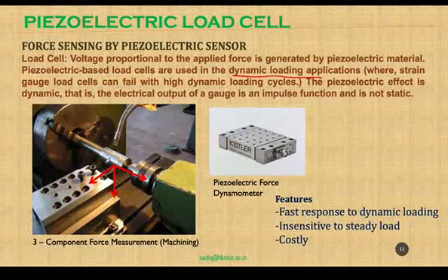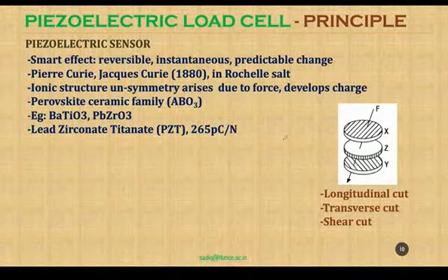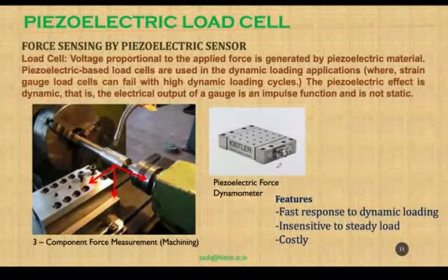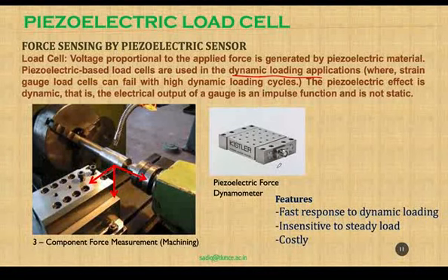Piezoelectric crystals are cut and placed according to the direction of force. Typically, there are three kinds of cutting done from the same crystal. It's a longitudinal cut, transverse cut, and shear cut. Depending on the direction of force, these crystals will be oriented so that they will be sensitive to force in that particular direction.